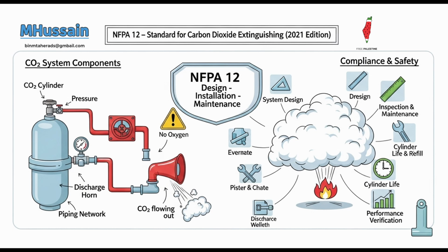Total flooding CO2 systems have been a common and effective method for protecting underfloor spaces in computer rooms and similar electronic facilities for decades. Total flood under the floor? Makes sense, it's enclosed. Right. The enclosed nature of these spaces, often filled with dense cabling, makes them ideal for total flooding, allowing the CO2 to reach every potential ignition point.